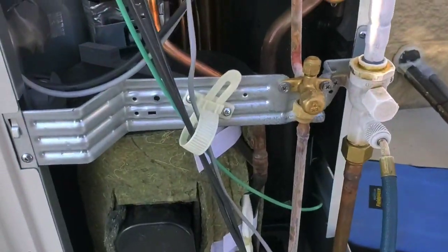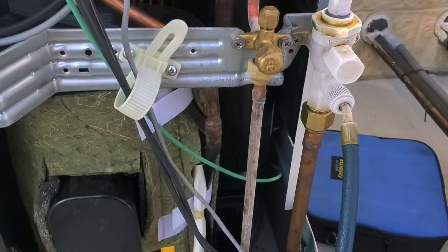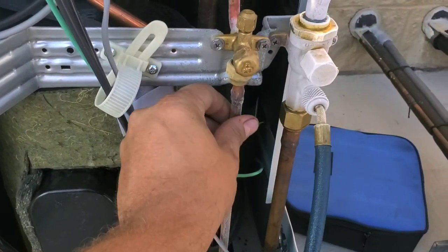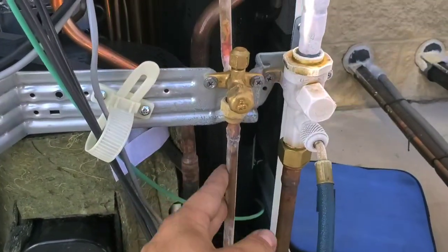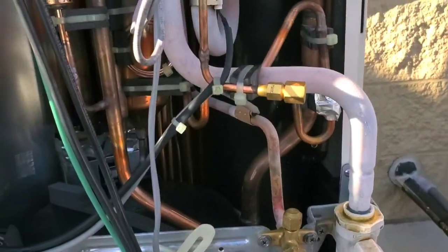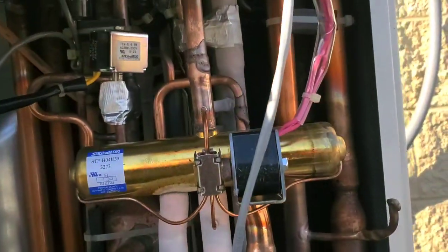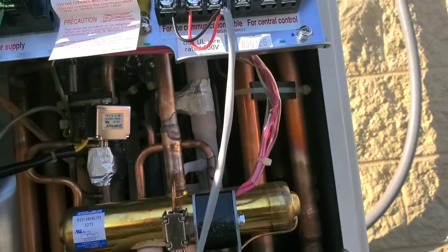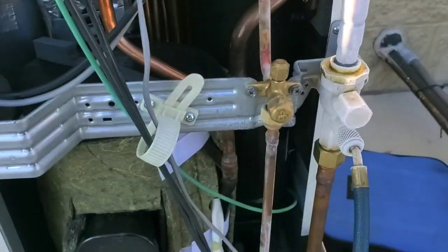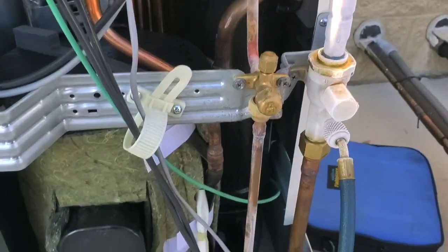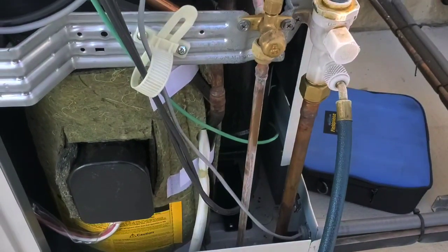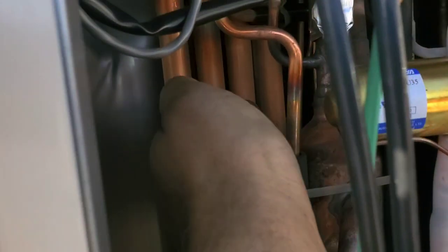Ice on the liquid line. What do you think about that? The compressor just spun down a little bit. So what's going on here is there's a liquid to suction heat exchanger, and I've got the suction line freezing cold. So it's literally cooling the liquid down below freezing. Is that cool? Our heat exchanger back there, and it's got ice on it.